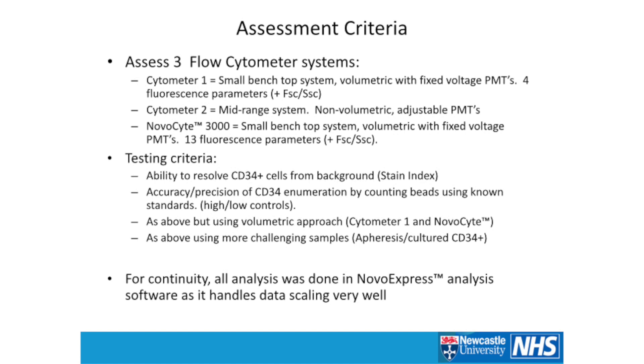Counting beads can be used on any of the systems. For those who know CD34 enumeration protocols, you can obtain standard samples with known numbers or percentages of CD34-positives — either commercially or from regulatory bodies for this assay in the UK. That gives you an idea of accuracy because you have a known range you should be within. We also moved away from beads using the volumetric approach on cytometer 1 and the NovoCyte, and then assessed more challenging samples: apheresis samples, which are a bit messier, and cultured or frozen-thawed CD34 cells.